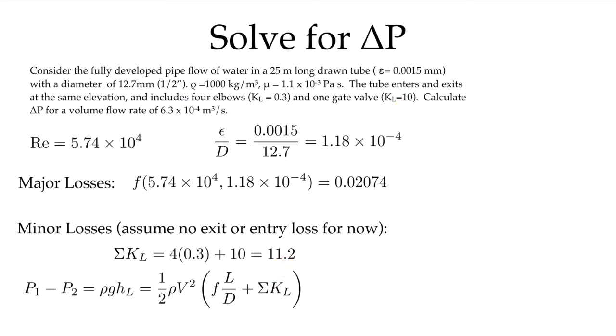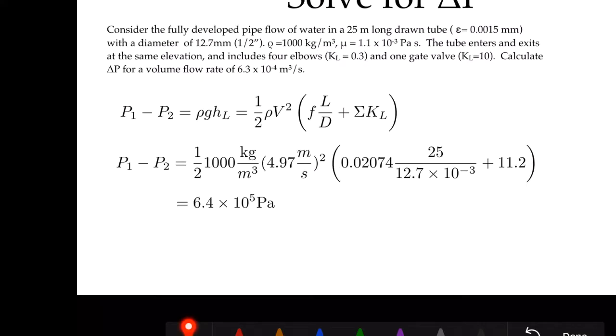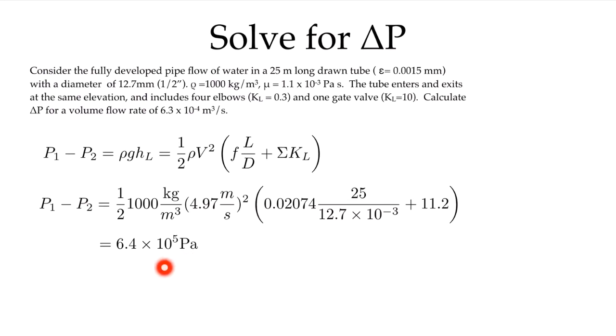The total is going to be 11.2. Now I can directly solve my P₁ - P₂ or the pressure drop across the pipe, as I know I've solved now for the velocity, I know the density, I've solved my friction factor, I know my L/D ratio, and now I know the sum of my minor losses. If I plug that in, I get a value of 6.4×10⁵ pascals.